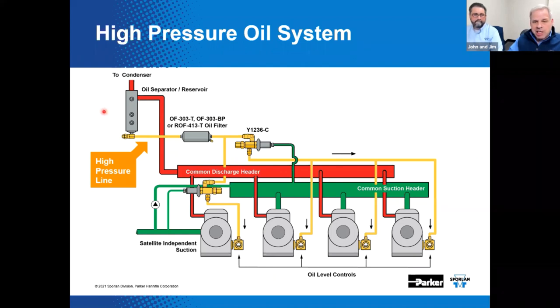Oil at discharge pressure leaves the separator reservoir when there's a need, and it comes through an oil filter, then goes to the Y1236-C. That oil pressure is at pretty high pressure and it's got to be reduced a certain amount to introduce it to the oil level control. The Y1236-C accomplishes the required pressure drop. Sporlan has used a 'Y' numbering sequence to identify OEM specials, so this is the 1,236 OEM special — it's also sold through authorized wholesalers.